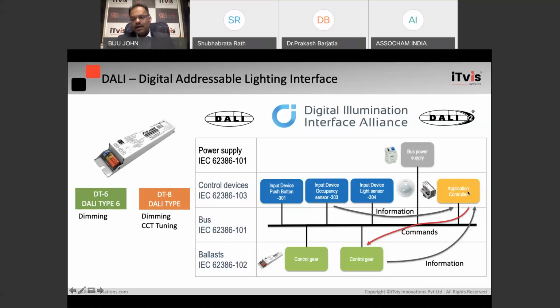And what commands does the controller give to the DALI driver? Come on, there is no occupant under you, because the sensor gave me a message saying there is no occupant in the room. You just go for an orientation light of 10%, or you just switch off. The controller is the one giving commands to DALI drivers. And what is the role of the bus power supply? It just powers up the bus connections.